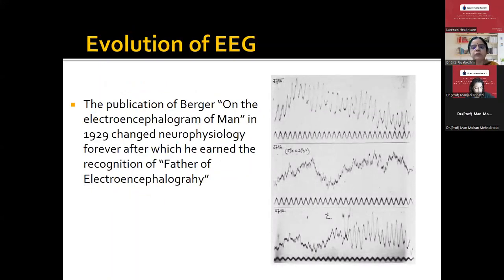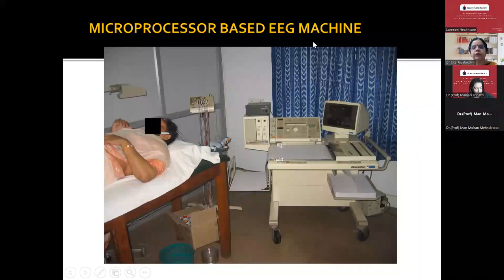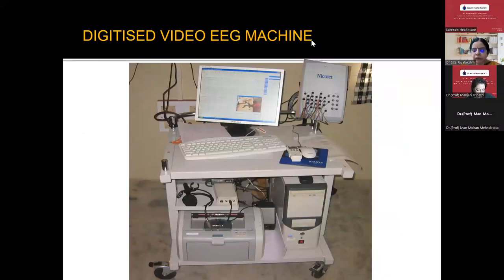As we already heard about the evolution of EEG — when you see the time of Berger in 1929, the recordings are not very clear, with a lot of artifacts, and the recording system used to be very big. The electrodes used were needle electrodes at that time. But over the years we are using microprocessor-based EEG machines and then digitized video EEG machines, which are very comfortable — we can mobilize these units even to the bedside in ICUs. But still there are a lot of artifacts, and it's very important that unless the neurologist knows, you cannot supervise your technologists to do a good quality recording.